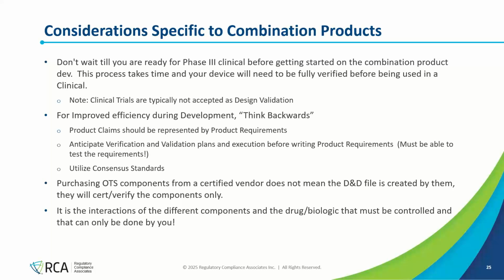Purchasing off-the-shelf components, syringes, plungers, needles, what have you, from a great vendor that has a lot of documentation behind it does not get you out of needing to do design controls. It helps you get design outputs, but you still need a full file because you're the one putting it together with the drug. And the off-the-shelf component suppliers are not going to take that responsibility on. So just something to keep in mind. A lot of people think, well, we're using this great BD syringe and they say it's certified to everything, I don't have to test it. That's not true. You have to test it once your drug is in it.